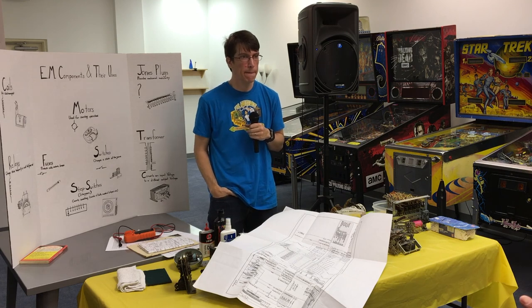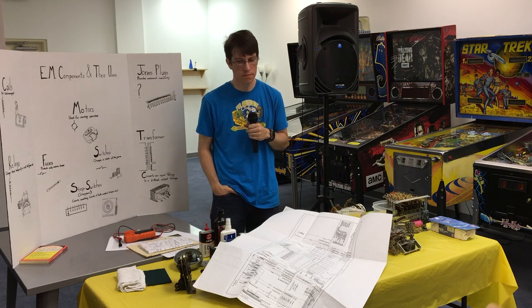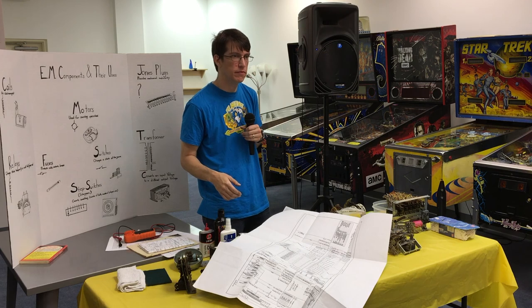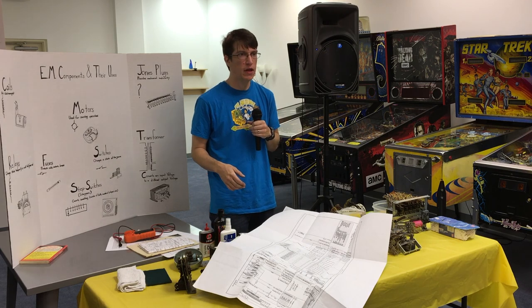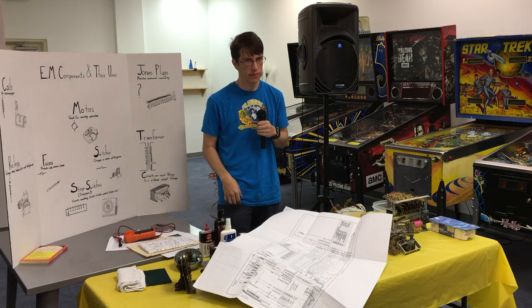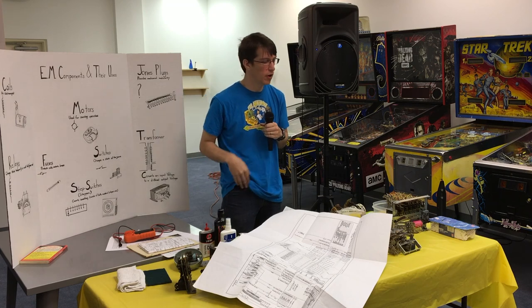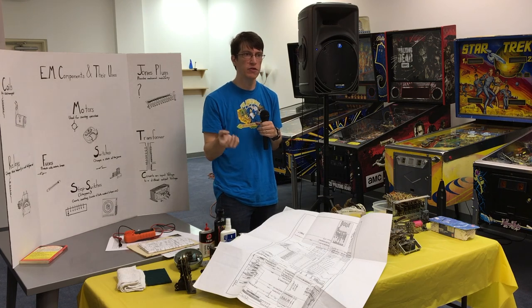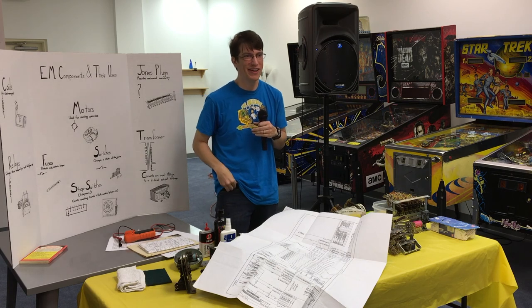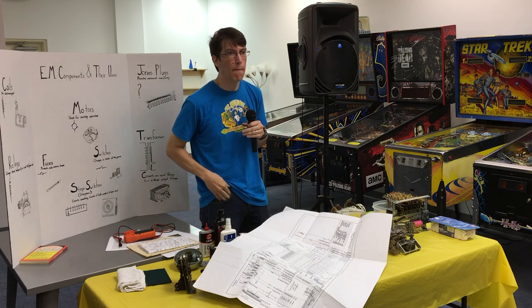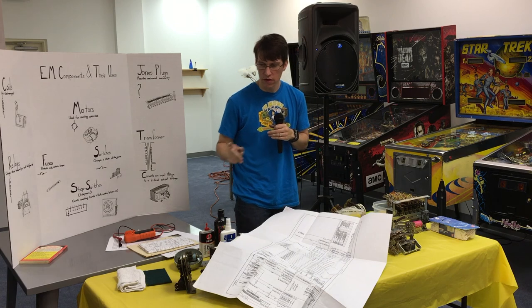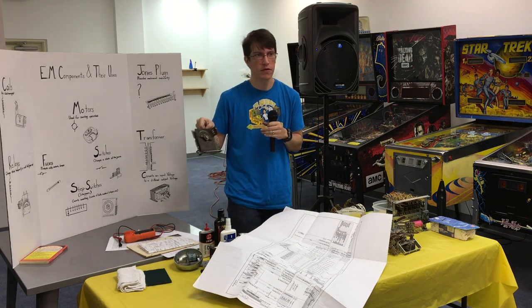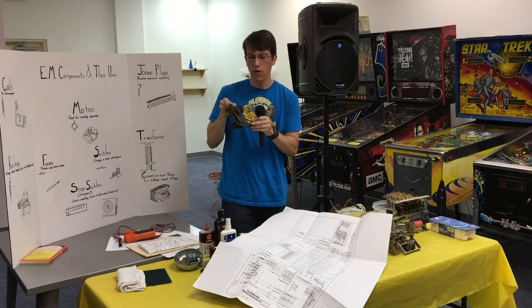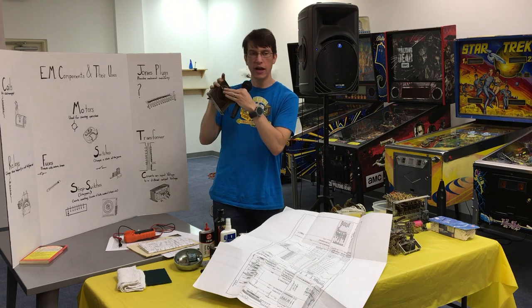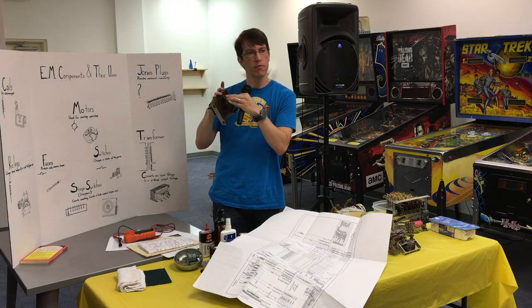So when you're adjusting the motors, just to see if they're turning, do you need to take them back to zero, or will they find zero on their own when you start them up? They'll find it. There's a switch that governs that movement, so it'll say, oh it's not at zero, keep going, now I'm at zero, stop. But the step switches - those you need to go back to zero, back to where they were when you disassembled them. If you disassemble it, that's where marking comes in - you need to mark them before disassembling.